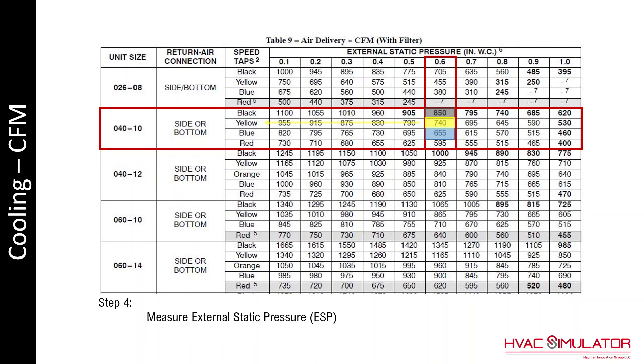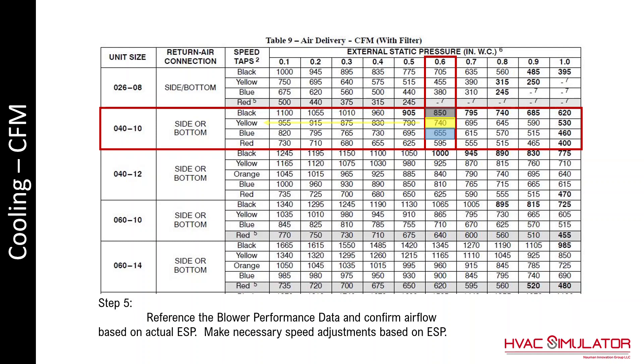Then measure the actual external static pressure and reference the blower performance data to see where the actual value falls. If the actual, in this example, were to be 0.7 inches of water column, then a judgment call needs to be made by a technician. At 695 CFM — is that a good value? It's a little below 700, but the technician may choose 795 CFM, which would be the black speed tap.